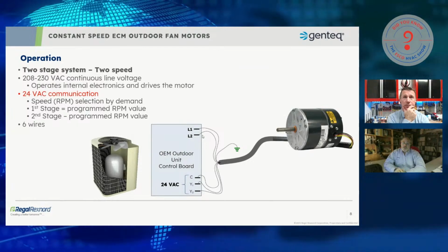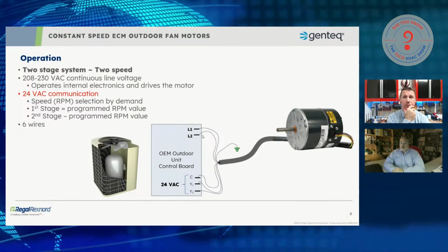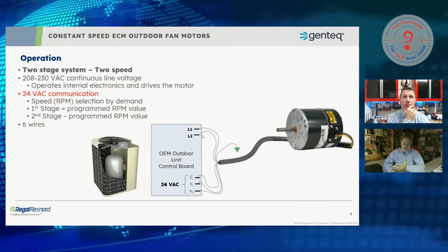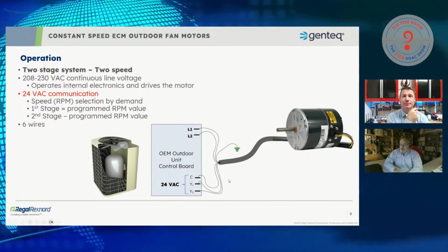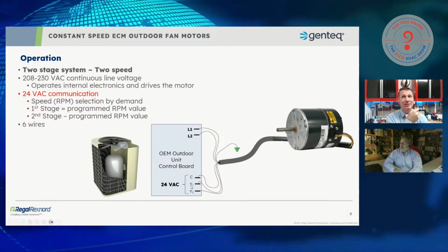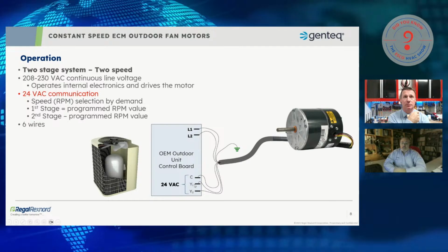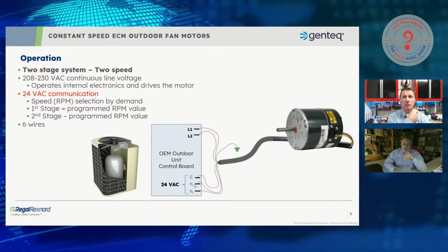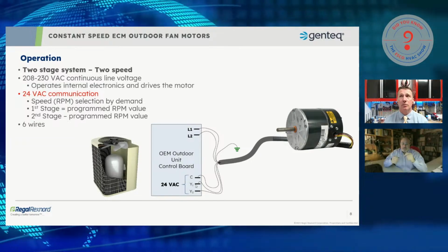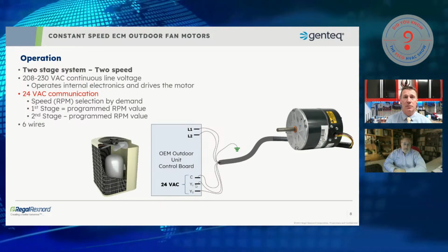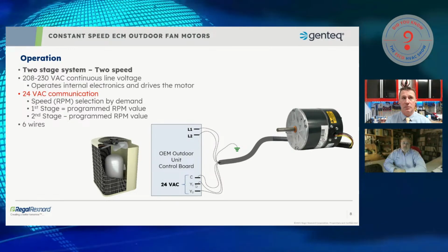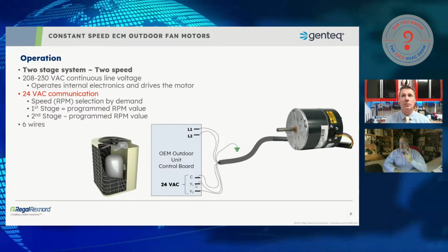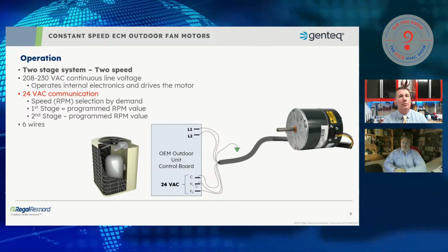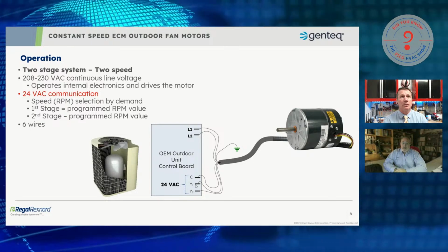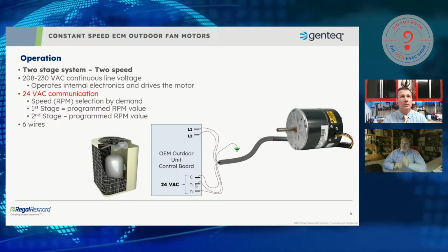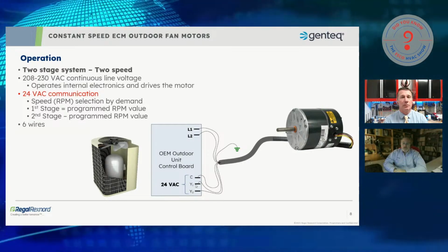The voltage that's going to turn the motor on and tell it what speed to run in the case of our discrete 24-volt AC motors is 24 volts AC. So on this board, I've chosen the nomenclature Y1 and Y2. If I'm in first stage, this board is going to energize 24 volts AC to speed 1, and that 24 volts is going to go into the motor. The microprocessor is going to see that I've got 24 volts on speed 1. It's going to operate at whatever RPM the manufacturer programmed for speed 1 first stage. If it goes into second stage, one of two things could happen. I could either terminate the voltage on speed 1 and energize the voltage on speed 2, or I could leave the voltage on speed 1 and add the voltage to speed 2.